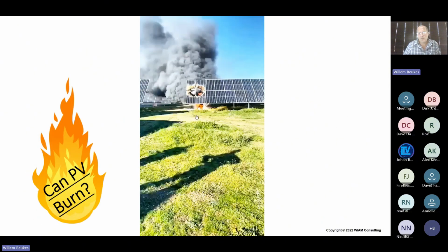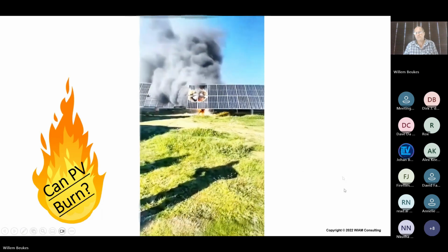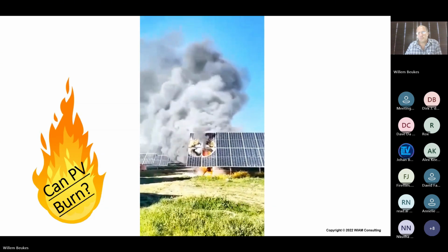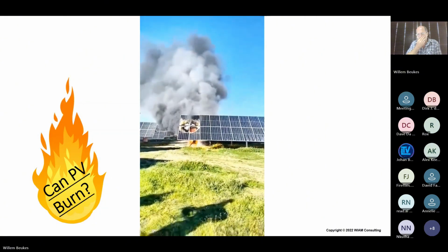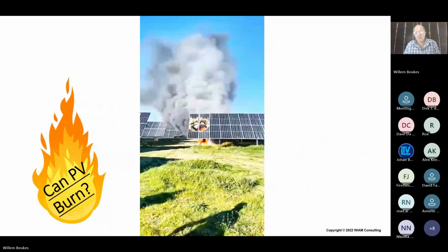Now, I know this slide has been used, but I want to go through it again just to show emphasis on certain aspects. What's happening when PV is burning? In this scenario, it's a DC combiner that's arcing, and that arc is actually burning right through the panel and creates an arc fire. That arc fire has two components: a heat component, and a component of smoke that gets produced by this arc generation.